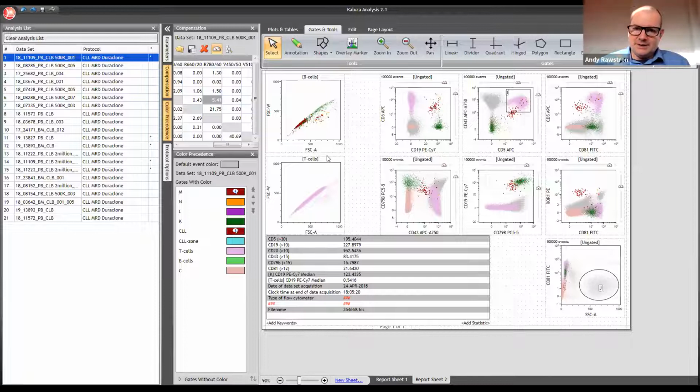So this looks really odd on all of the DuraClone tubes that we've run, I'm afraid, because of the fact that the samples are a day old, and secondly because we weren't using the correct lysis approach. We weren't using the Coulter's recommended lysing. We were using a BD lysing agent, which didn't give us complete lysis in the setting that we were using with lots of cells.